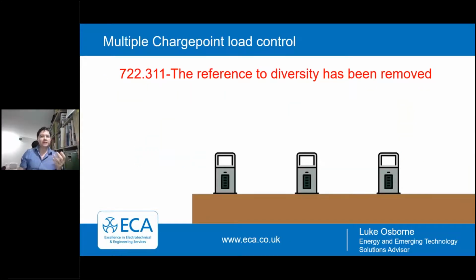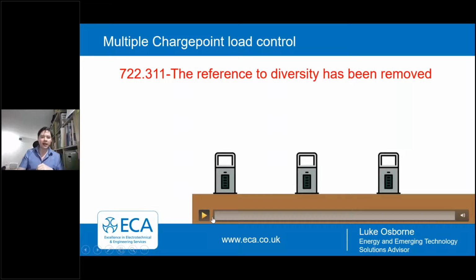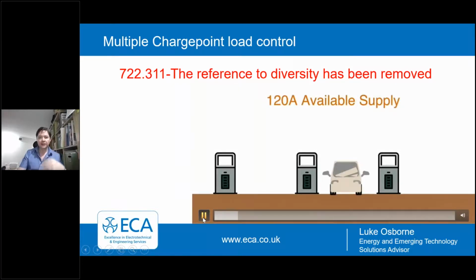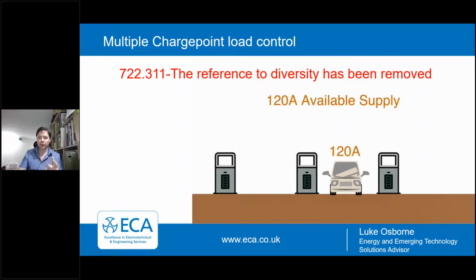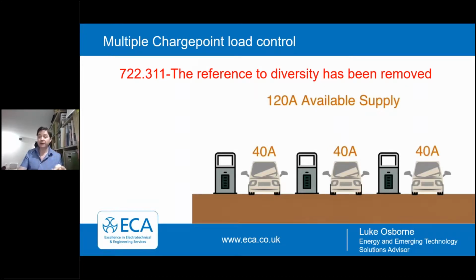So the reference to diversity has been removed, and the reason for this is more of the onus has been put on load control. And load control, we'll see how that operates in this short video. If you had a 120 amp supply and one vehicle, that vehicle would get 120 amps. If there were 3 vehicles, that would reduce down across the charge points to 40 amps apiece, and 2 vehicles would become 60 amps apiece.